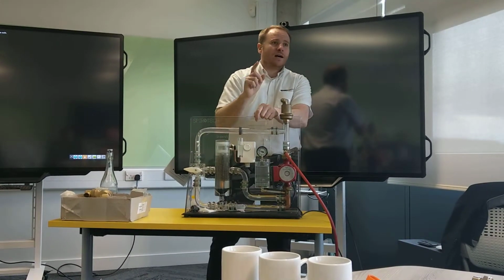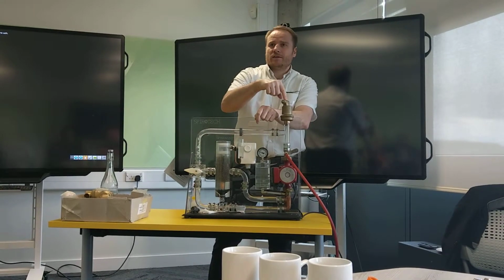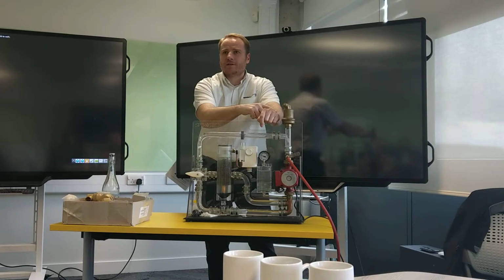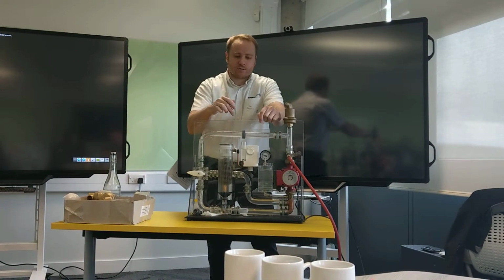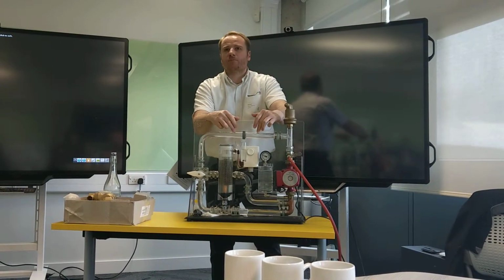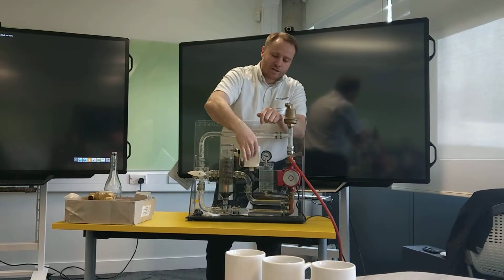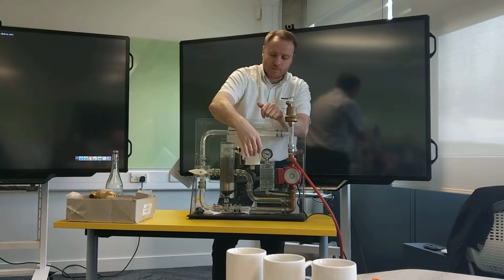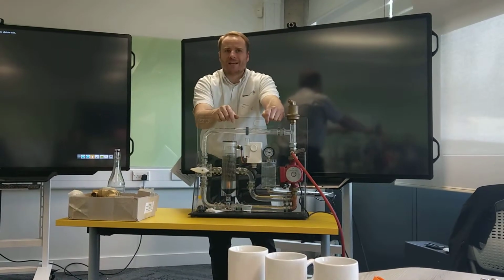And a lot of people say, I don't need a deaerator, I have an AAV. Well, this is a very highly engineered AAV, it comes with a 20-year guarantee. But its function is not to remove microbubbles or free air when there's movements of water. It's only when that stops. Then you accumulate a free air bubble, blow it, and then it can remove it. But while there's movements of water, they are near enough redundant.